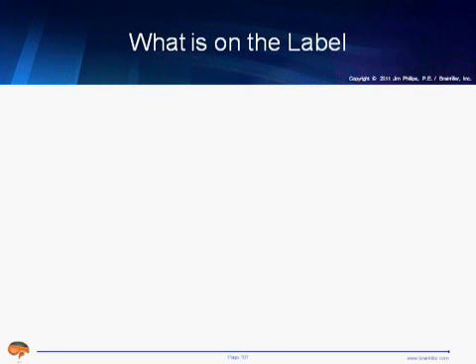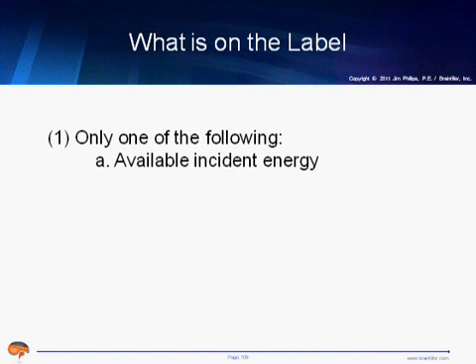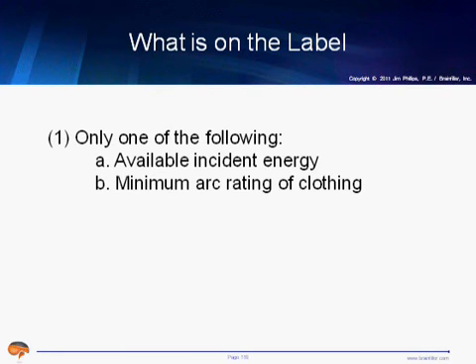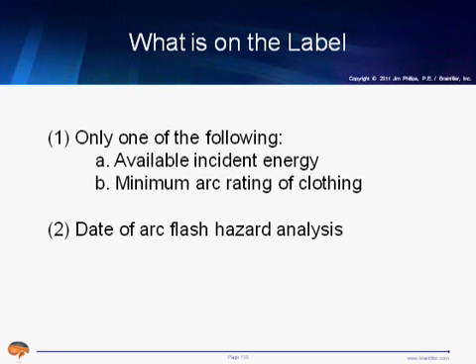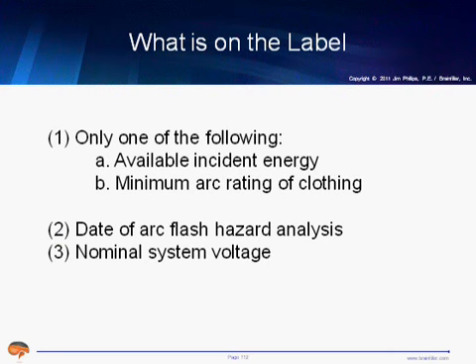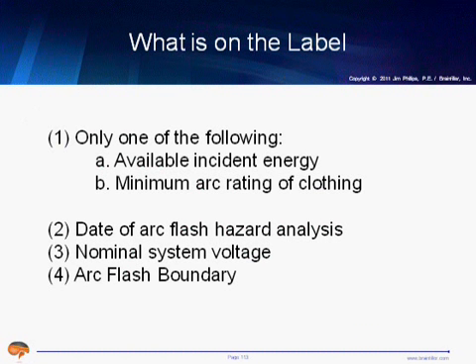The question is now, okay, what goes on the label? Beginning in 2012, the requirements are that you either have the available incident energy, which would most likely be derived from calculations, or the minimum arc rating of the clothing. So if you choose to use, for example, 8-calorie or 12-calorie protection, that would go on the label, as well as the date of the arc flash study, the nominal system voltage, as well as the arc flash boundary. So there are increased requirements of the data, the information that's going to go on the label.